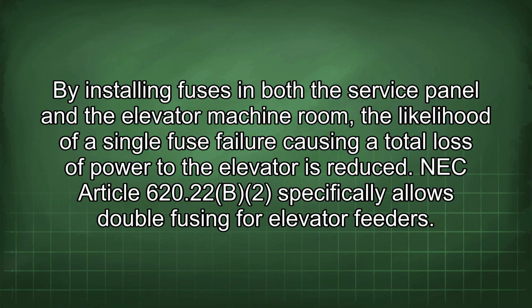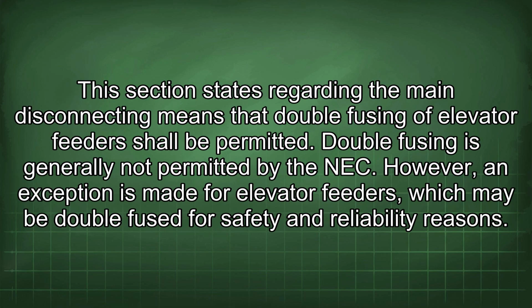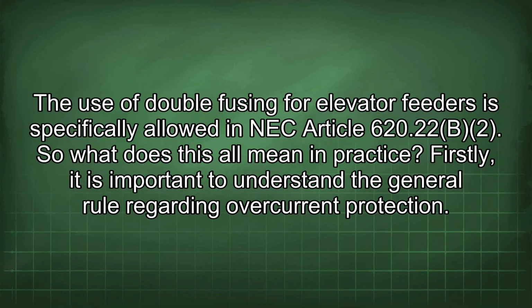NEC Article 620.22b2 specifically allows double fusing for elevator feeders. This section states regarding the main disconnecting means that double fusing of elevator feeders shall be permitted. Double fusing is generally not permitted by the NEC. However, an exception is made for elevator feeders, which may be double fused for safety and reliability reasons. The use of double fusing for elevator feeders is specifically allowed in NEC Article 620.22b2. So what does this all mean in practice?